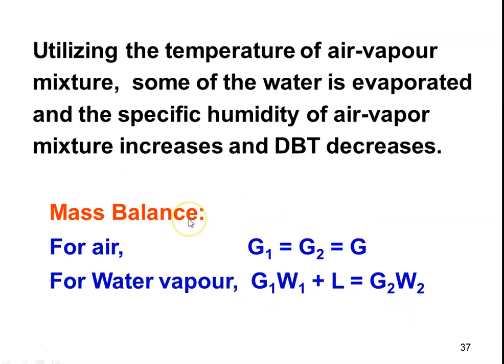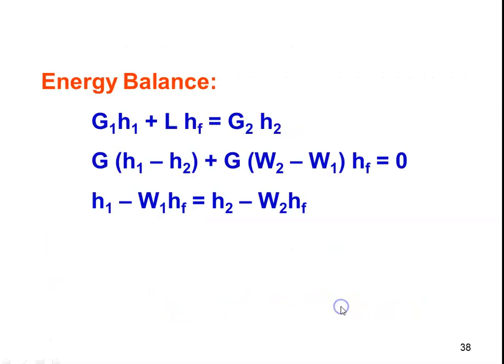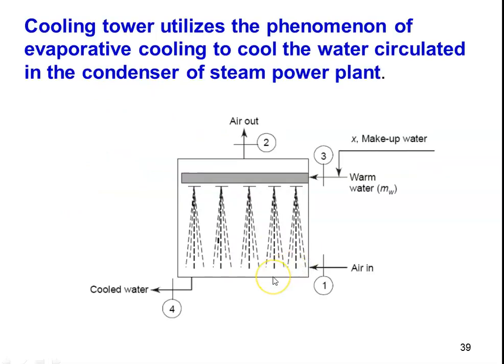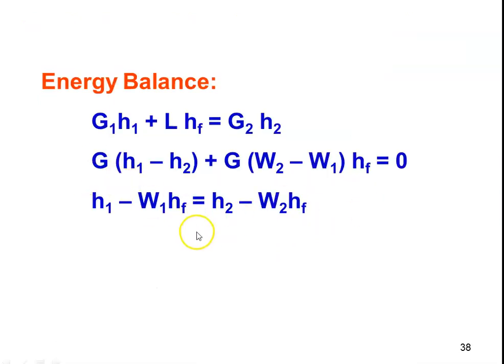Water is sprayed in the duct where air and water vapor circulate, maintaining constant enthalpy while adding water vapor. For the mass balance: G1 = G2 = G for air; G1·W1 + L = G2·W2 for water vapor. Energy balance: G1·H1 + L·HF = G2·H2, which gives H1 − W1·HF = H2 − W2·HF — this is the energy balance for evaporative cooling.